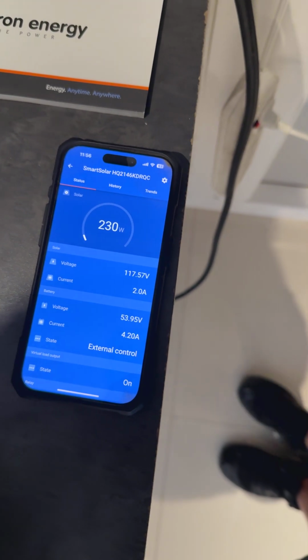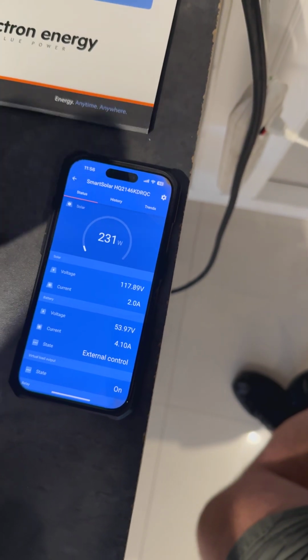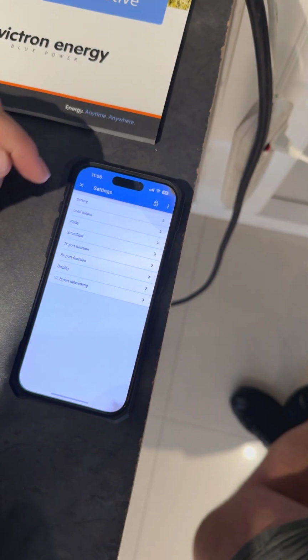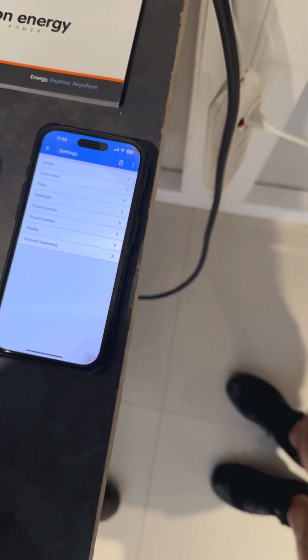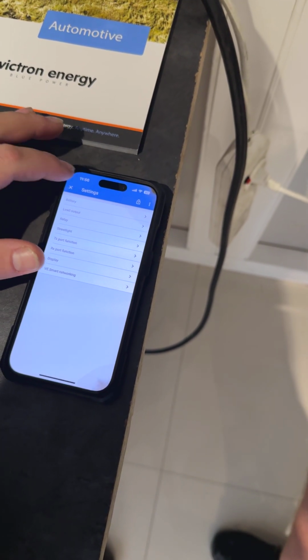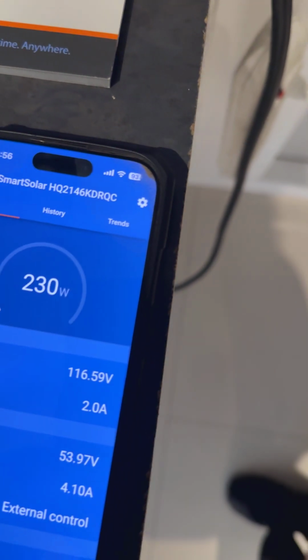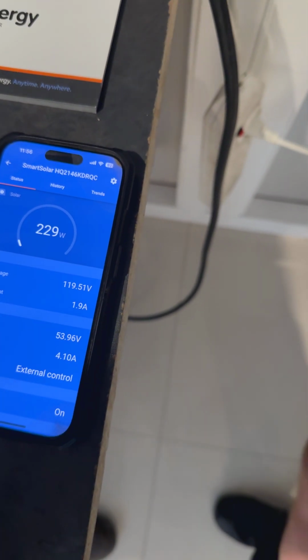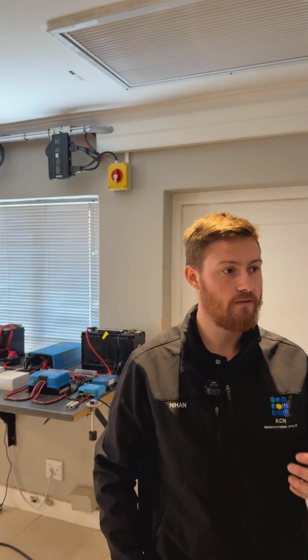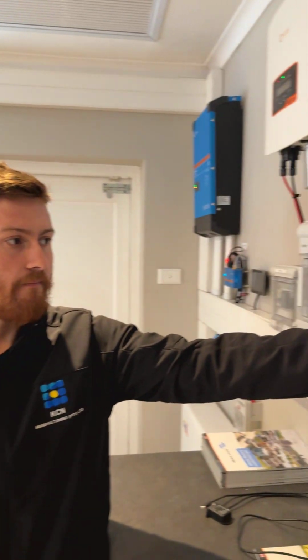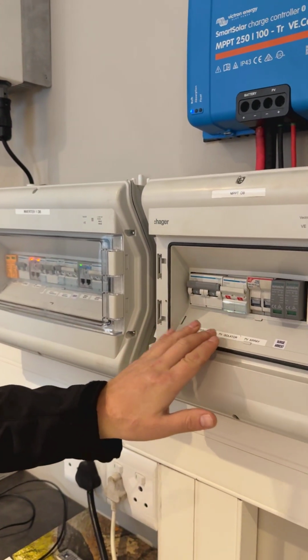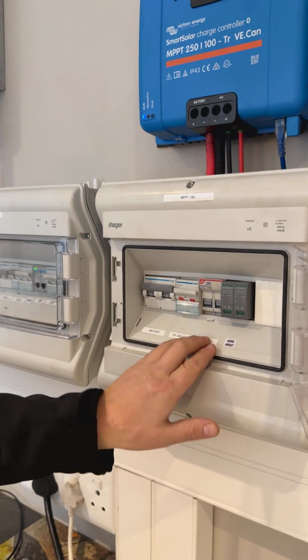If you have an older MPPT that needs updating, it will block the settings tab and say you cannot change settings before you update. If you have an older firmware version, anything before 2021 - this one is a 2021 model - we recommend, based on our own experience and past mistakes, that it's better to update by switching off the battery side and only updating from the PV side.